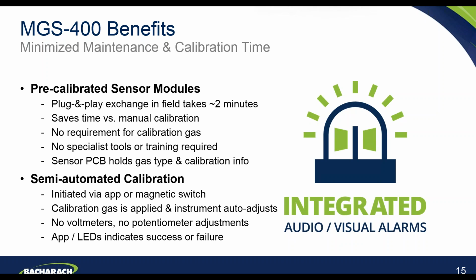So once you've initiated the calibration mode via the app or with the magnetic switch, you simply apply your calibration gas, switch that on. The instrument makes all of the necessary adjustments. There's no need for any use of voltmeters. There's no need to adjust any potentiometers. You don't need to even take the faceplate off the detector itself. Very quick and easy and straightforward to do. Once the calibration is complete, you will receive a notification on the app, if you're using the app, that it's been completed and has been successful or has failed. And if you're not using the app, the LEDs on the unit will indicate whether the calibration was successful or not.